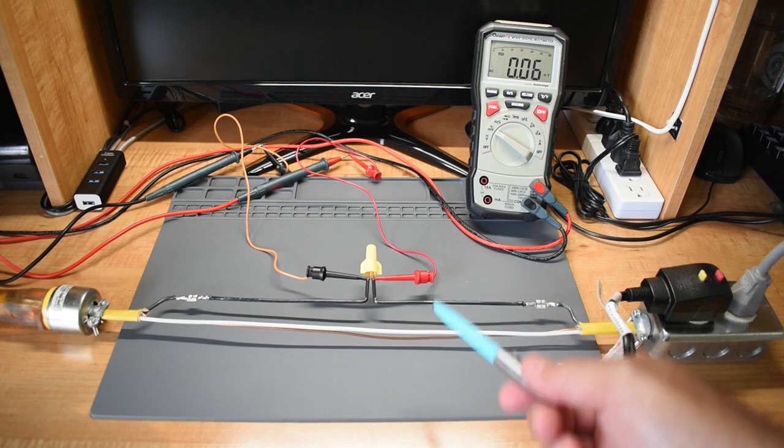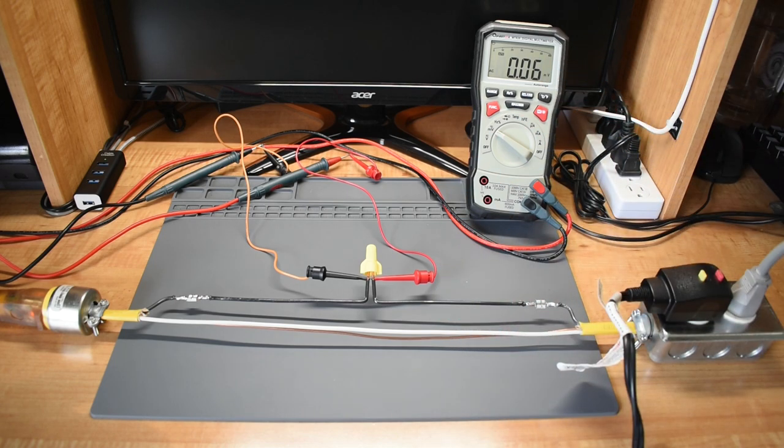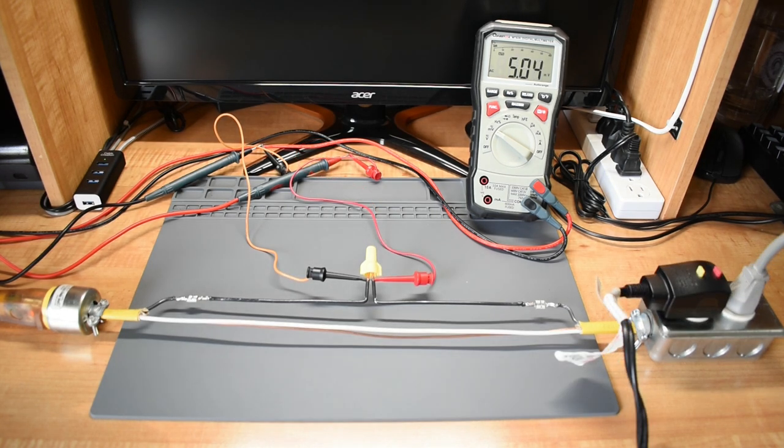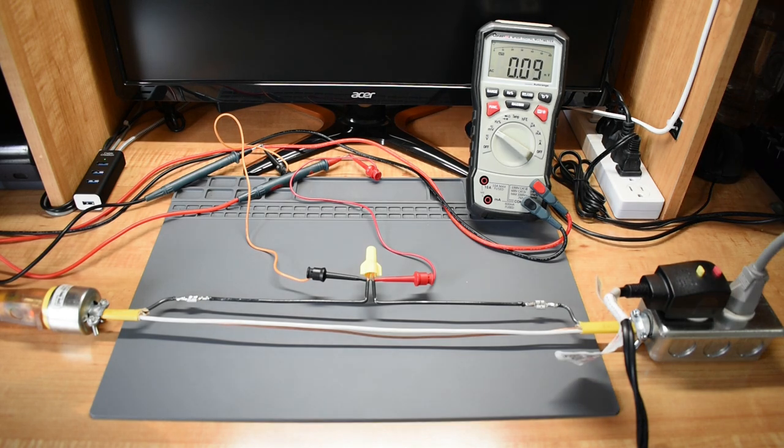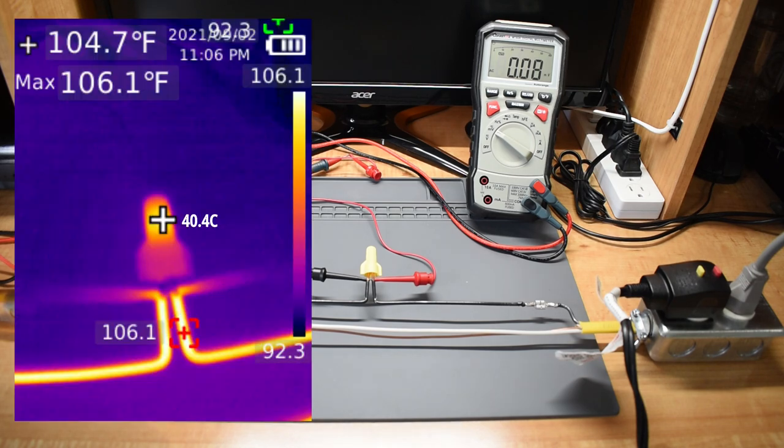Now the wire nut is going to be tested. Just like before, I'm going to deduct 0.05 millivolts. Okay guys, test complete, fifteen minutes, just a little bit over five millivolts, so slightly higher than the uncut wire. And right here you can see the temperature of the wire nut under load just before the test ended.